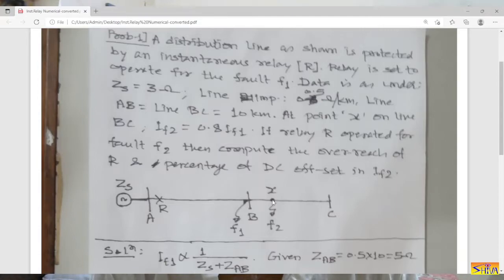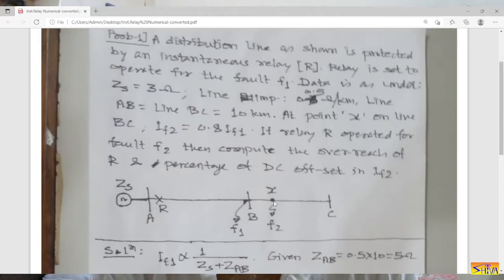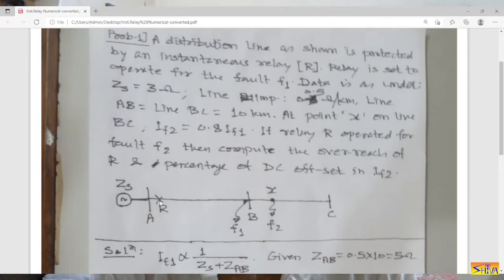At point X on line BC, fault current IF2 equals 0.8 times IF1. As we move away from the source, the magnitude of fault current reduces, so at point X it is 80% of IF1. If relay R operates for fault F2 at X, we need to compute the overreach and the percentage DC offset in IF2. Without DC offset, IF2 is only 0.8 IF1 and relay would not operate, but due to the DC offset the actual fault current increases, so relay R is overreaching.